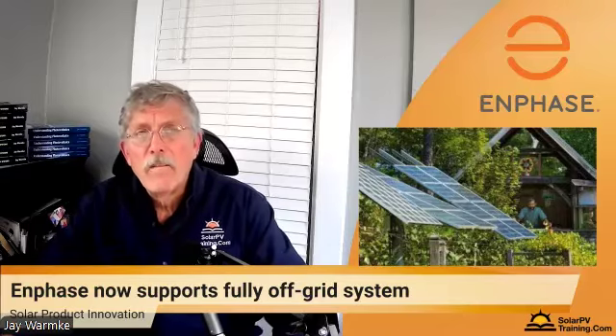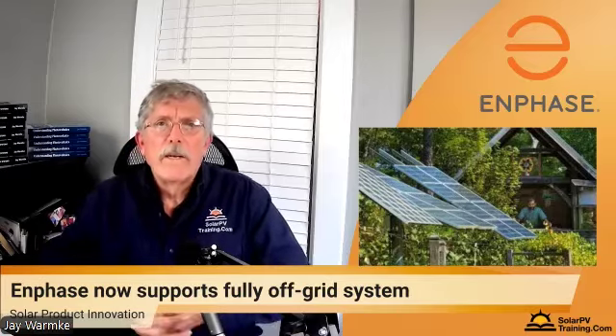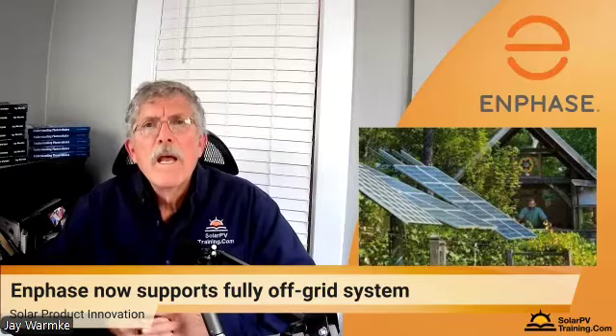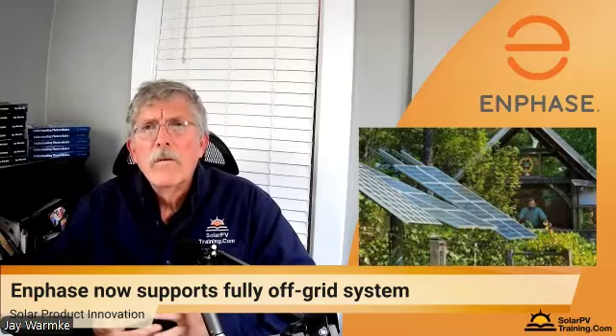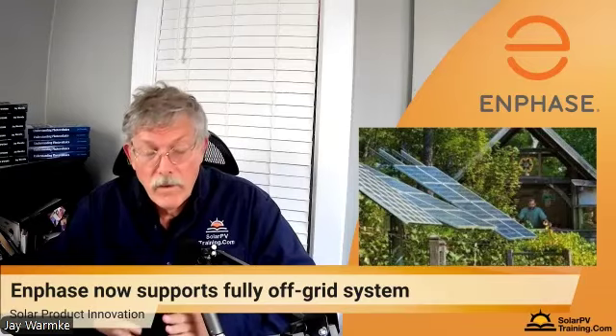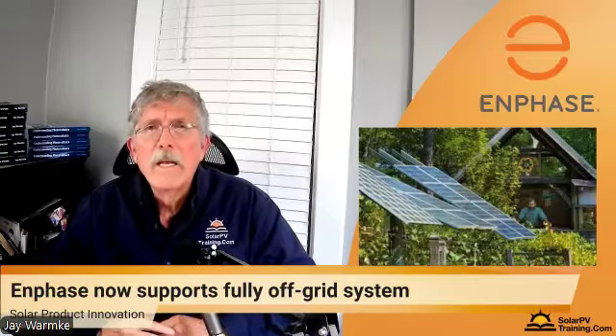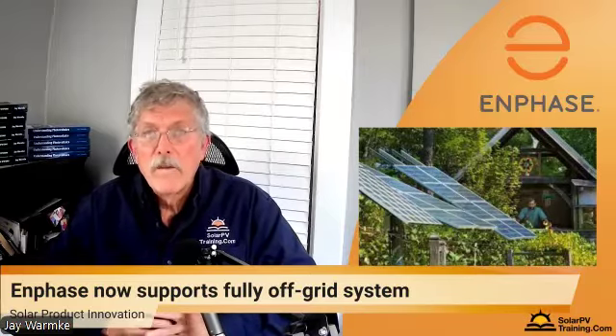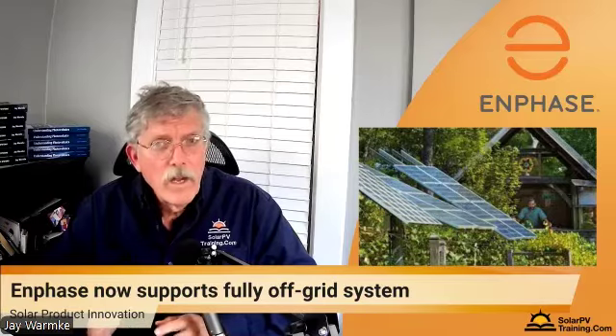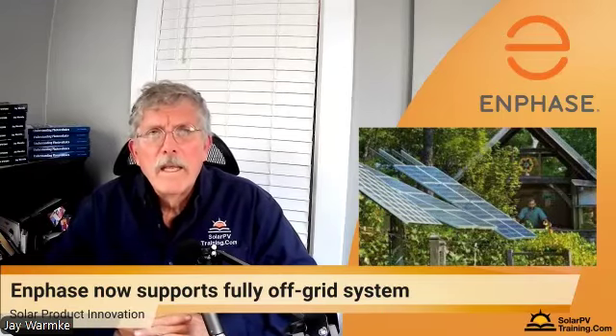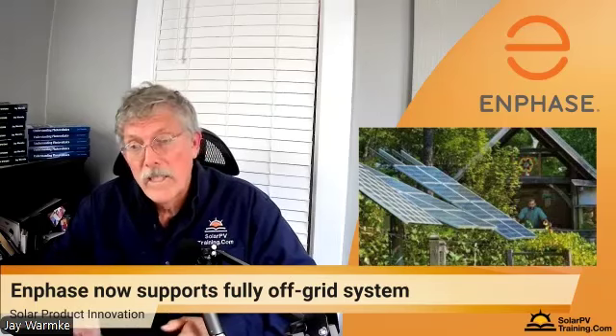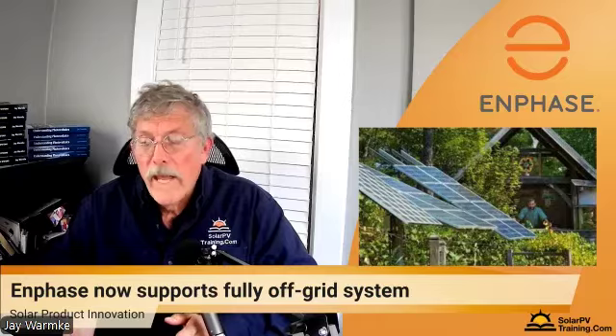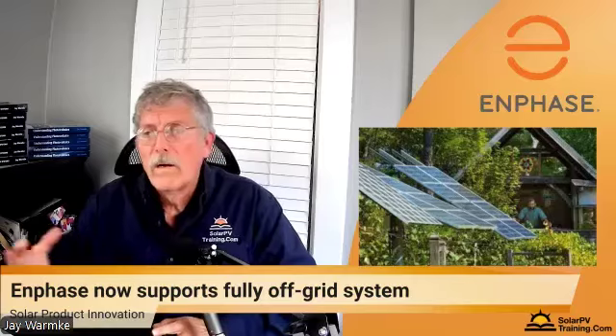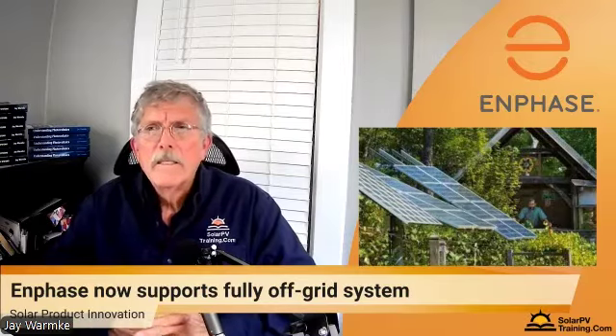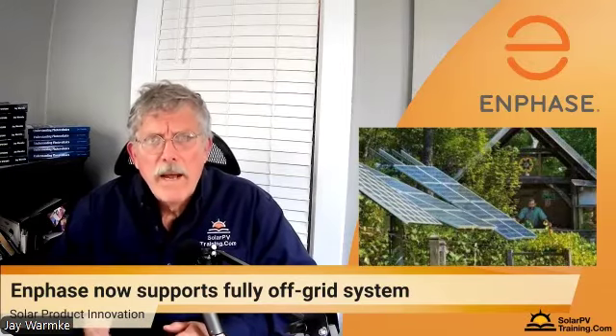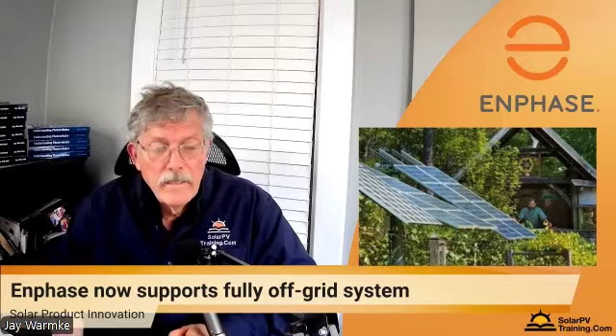Speaking of which, Enphase just added a new off-grid commissioning profile to their systems. This enables the system controller within their latest generation of products to operate fully without utility connection, making it a true standalone system. A few dozen homes, only a very small amount, are fully off-grid according to Enphase at the moment. The stack requires three things: an IQ battery, the IQ8 series microinverters, and a third-party generator connected in. Together, they form a microgrid that can power loads and recharge the battery when islanded or off-grid.